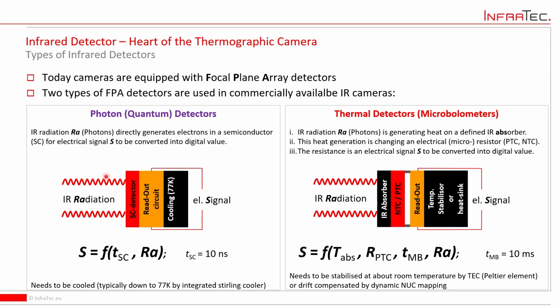So the way these work is you have the infrared radiation reaching the sensor surface through the optical system, and there's a photovoltaic effect associated with these that results in an electrical signal that can then be easily converted to a temperature with the help of the calibration curves.